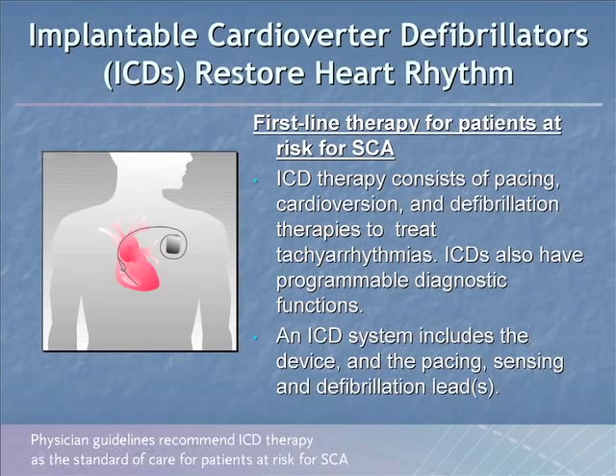The implantable cardiac defibrillator restores heart rhythm and is the first-line therapy for patients at risk for sudden cardiac death. These devices provide pacing, cardioversion, and defibrillation treatments, plus programmable diagnostic functions. All modern defibrillators can also serve as a pacemaker — if there's no pacemaker indication, that function can be programmed off while the defibrillation capability remains active. The device consists of the pulse generator — the computer and brains — and leads, which are two-way streets sending signals back and delivering shocks.